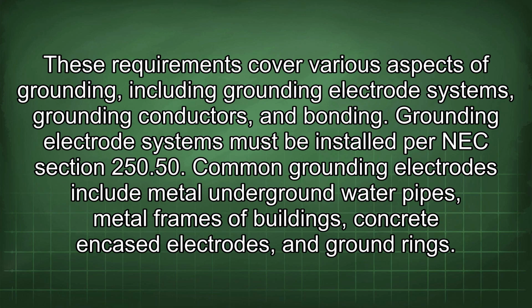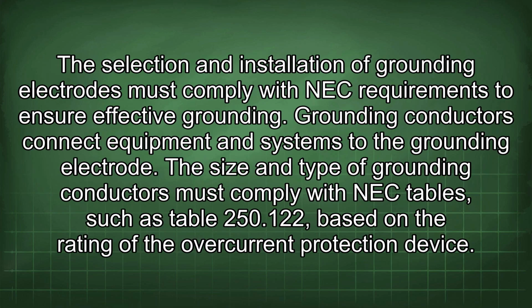Grounding electrode systems must be installed per NEC section 250.50. Common grounding electrodes include metal underground water pipes, metal frames of buildings, concrete encased electrodes, and ground rings. The selection and installation of grounding electrodes must comply with NEC requirements to ensure effective grounding.